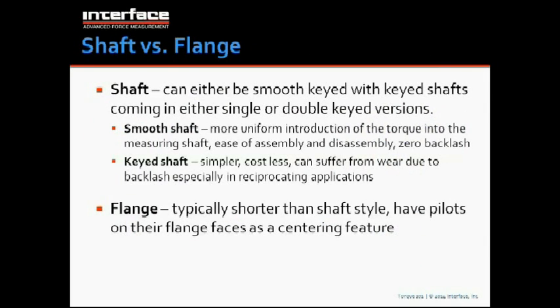When you're talking about torque sensors, there are two basic types that come up frequently, and that would be either shaft or flange style. A shaft type sensor has a shaft, and the shaft can either rotate or not. There are certainly shaft style reaction sensors, and most of them are rotary though. And the shaft is either going to be smooth or keyed. And then there's also flange styles. And the flange is shorter, and it may bolt in easier, maybe not.